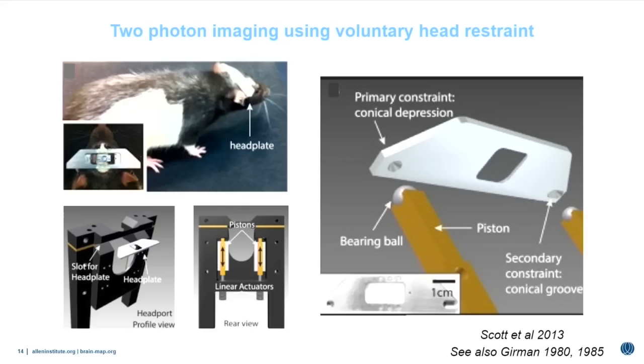We implant a titanium head plate in the head of the animal and teach them to slide their head and head plate into a slot in one wall of the behavioral training chamber, at which point pistons clamp the head in place. This is actually a miniaturized kinematic mount — on the base of the head plate are two features: a conical depression and a groove. The clamping mechanism drives two stainless steel ball bearings into the bottom of the head plate, which stabilizes head movements to within a few microns for two-photon microscopy, and registers the head to the exact same position on each insertion.